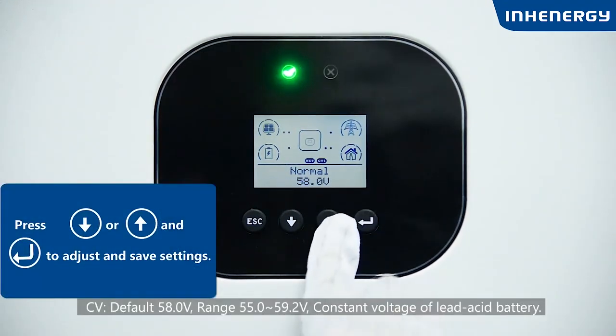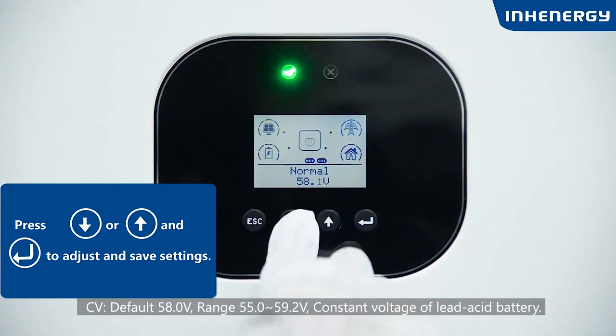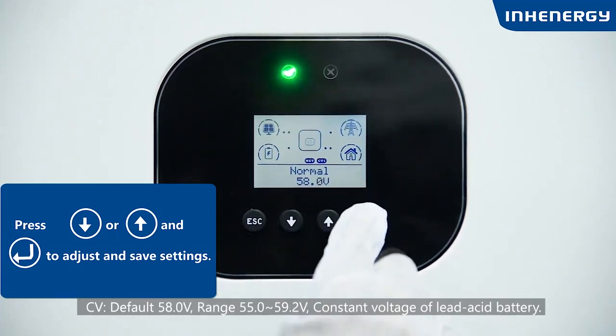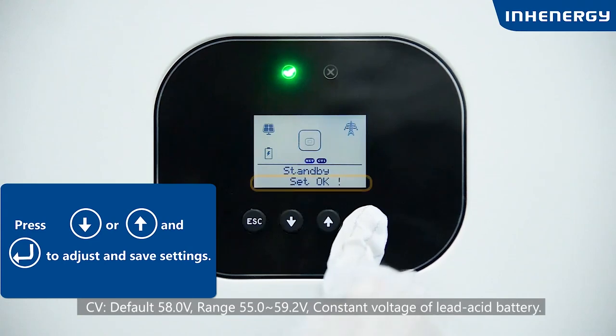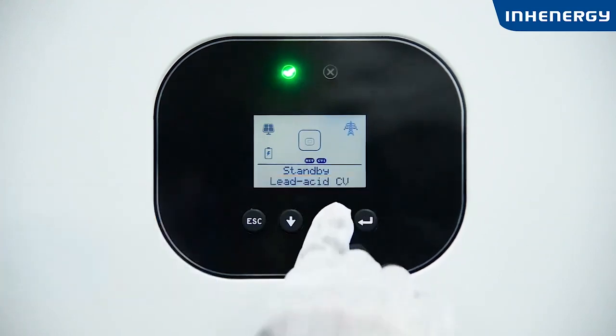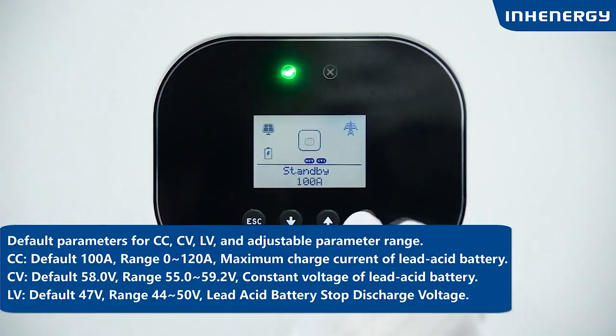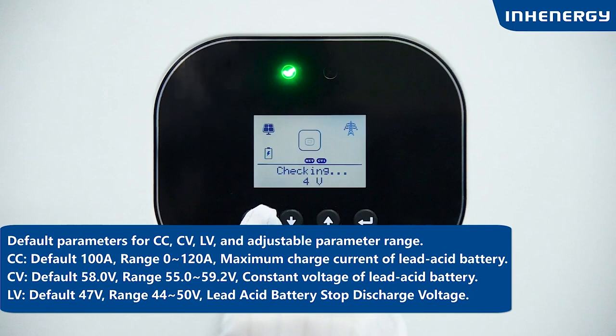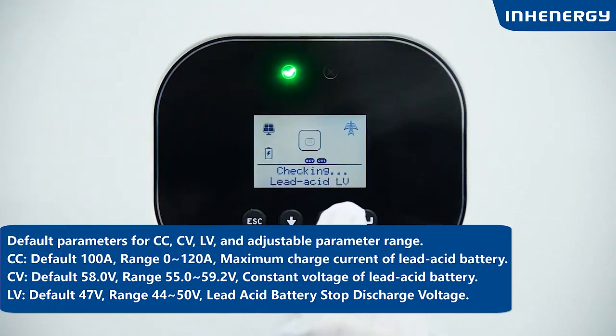CV default 58 volts, range 55 to 59.2 volts, constant voltage of lead-acid battery. CC default 100 amperes, range 0 to 120 amperes, maximum charge current of lead-acid battery. LV default 47 volts, range 44 to 50 volts, lead-acid battery stop discharge voltage.